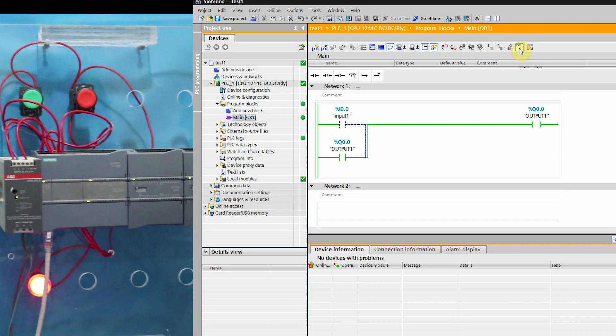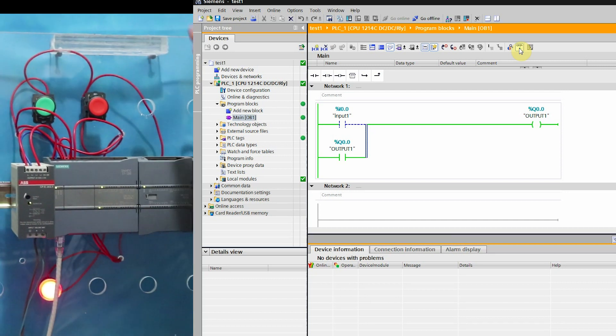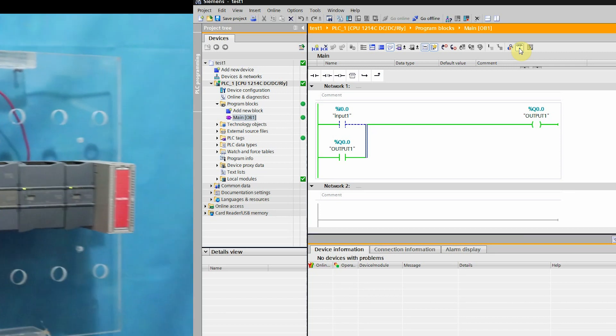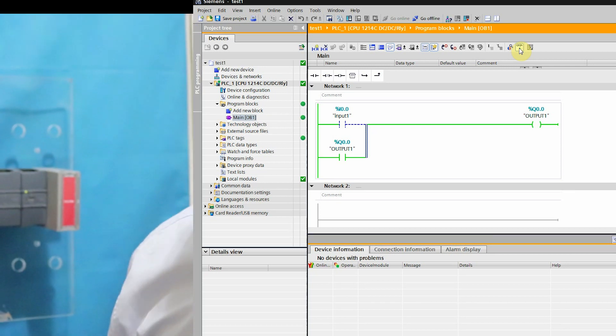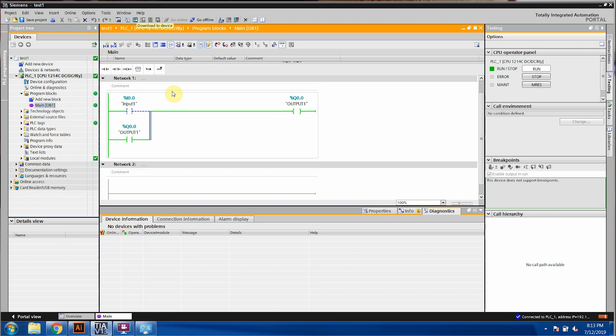For that, we need to have another button — this should be start, and another stop button should be there. Let's go back to the programming. In the simulation you can also see: when we press the button, at the same time our output is high. When our output is high, we are using a feedback of that output as a normally open contact in parallel to our input. From the input point of view this circuit is open, but we have a parallel feedback of the output that is making that circuit close and we are getting the output.